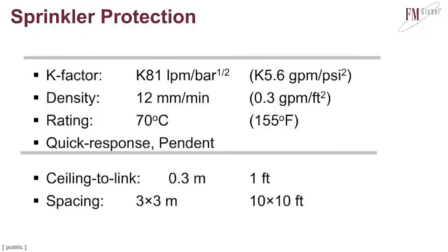There's really 2 ways you can handle protection for this type of test. The first one would be to try to determine the amount of sprinkler protection you need to provide to adequately protect the hazard. The other way to do it is to look at the level of protection you currently have in the types of facilities where we're seeing energy storage systems. And that's the approach we went with.